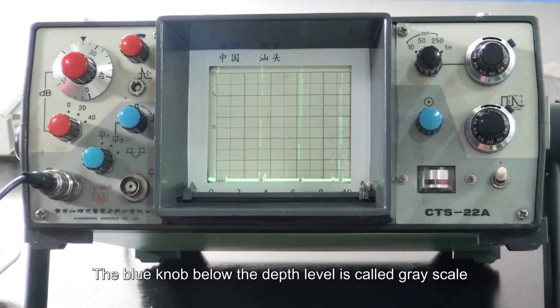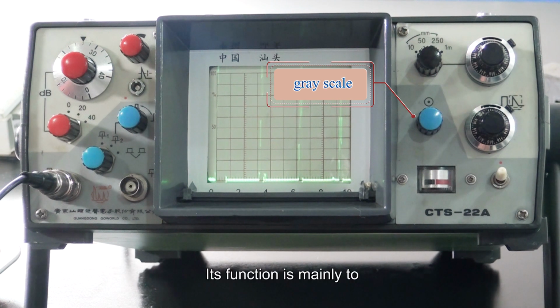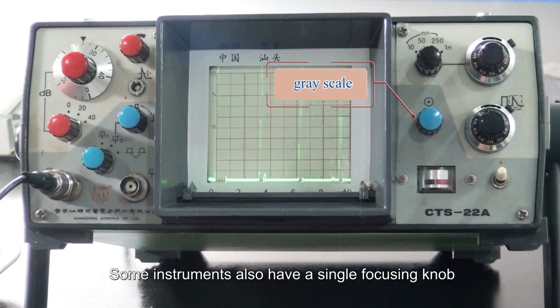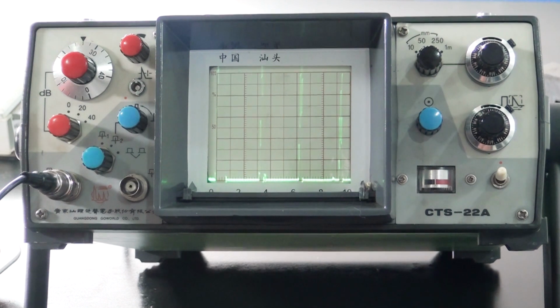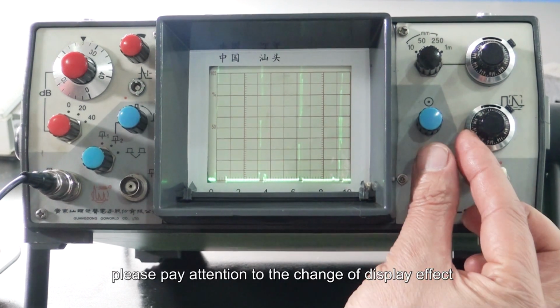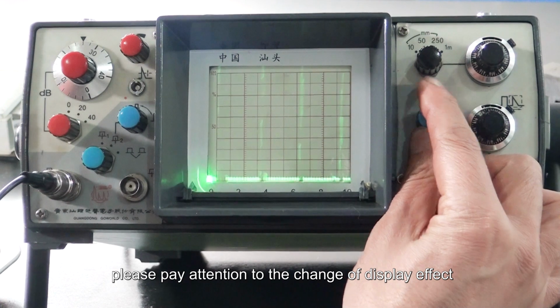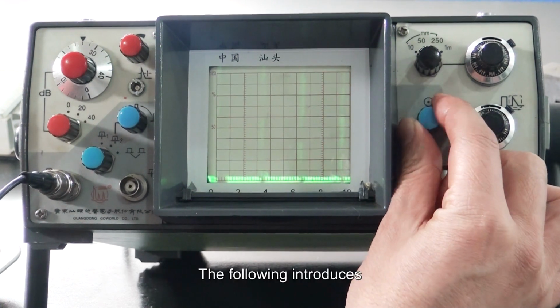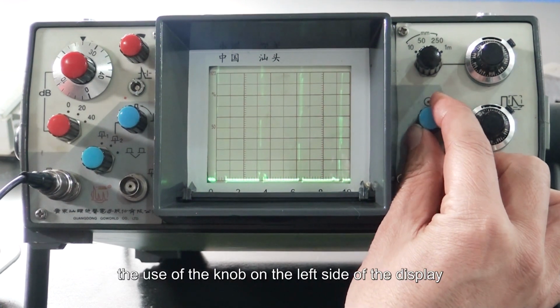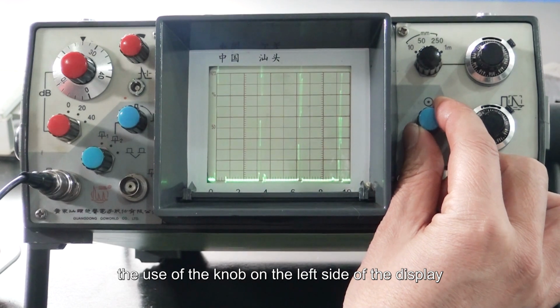The blue knob below the depth level is called grayscale. Its function is mainly to change the brightness of the display. Generally, it also has a focusing effect. Some instruments also have a single focusing knob. Next, please pay attention to the change of display effect. The following introduces the use of the knob on the left side of the display.